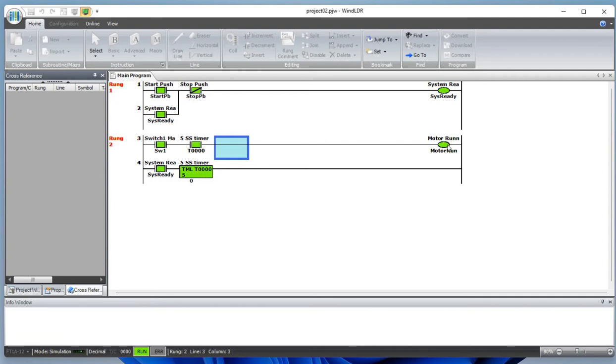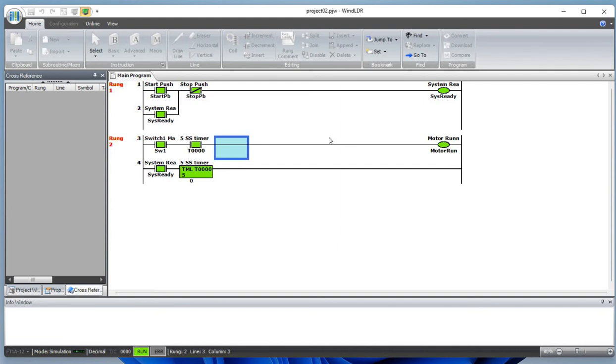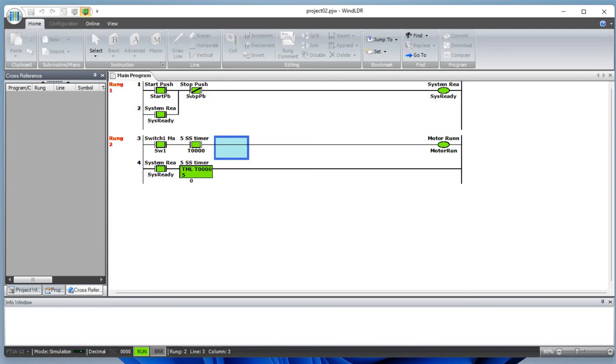You saw that the timer was running, and once the timer reaches five seconds, the motor turns on. Why do we need to delay the timer to run the motor? In many applications, if you have a number of motors, then to reduce the amount of inrush current at the same time, you will have a different time to start the different motors. That's how you work on limiting the inrush current.